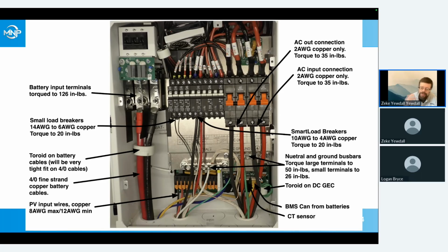That's not what we typically do. We always want to get all the big wires in first and then deal with all our little stuff. But it's really a lot better if we get our smaller wires, our PV array, and all of our COM wires in there first before we start pulling in our 2-gauge and our 4-aught for our big wires and covering those up. Eventually, maybe we can change some of the layout in there, but for right now, order of wiring is do all your small stuff first and then run your big wires in, and it'll be a lot easier.